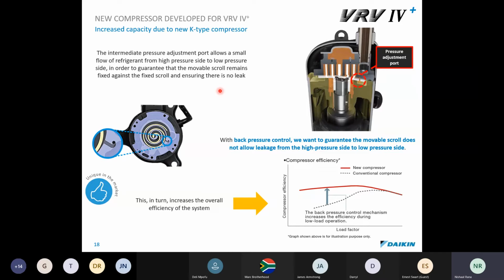You've got to look at the amount of work done. The more work you are doing, the more power you're going to consume. That's the thermodynamic or mechanical laws. So what you want to do is reduce doing unnecessary work. With back pressure control, we want to guarantee that the movable scroll does not allow leakage from the high pressure side to the low pressure side. Because what's the point of going through the compression cycle and then leaking it back into the system? It doesn't make sense. You're doing work for no reason. So by what we've done with the back pressure control, we've also increased the efficiency of the system.